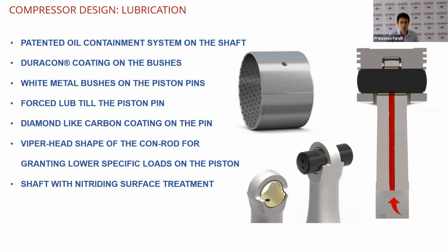We have Duracon coating on the bushes. All the connecting rods, the small ends, have white metal bushes. As I said, we have lubrication up to the piston pin. That is one of the most stressed parts of the system. And the pin is made of DLC, and DLC means diamond-like carbon coating. This material basically can work quite well even with poor lubrication. So even with very low oil or with oil with low viscosity, you will not have any problem of lubrication.